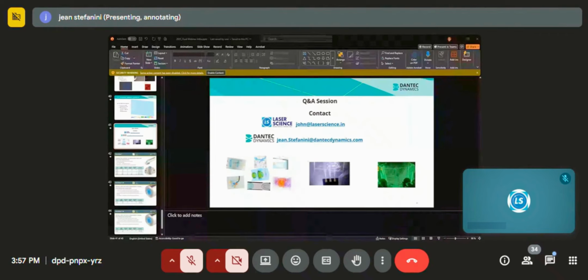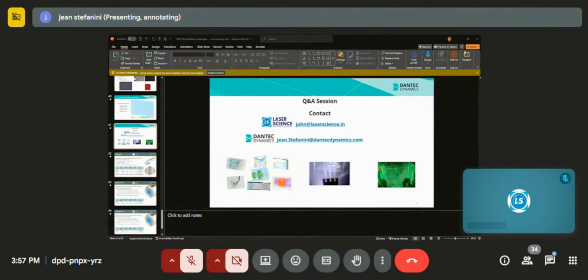There's a question about CTA: is the mini CTA compatible with some National Instrument cards? Yes, it's compatible with some National Instrument cards. The only thing is our software only supports a couple of types of National Instrument cards. The mini CTA gives you just an analog signal, but you can record with any kind of A to D converter - it doesn't really matter, as long as it matches the requirements in terms of voltage and resolution. The only thing is, if you want to use our software package to record the signal, calibrate, and have an integrated system, the NI card needs to be compatible with our software - that's all that's required. But we have people who bought the mini CTA, have their own NI card, record the signal, and do their own processing. So the answer is yes.